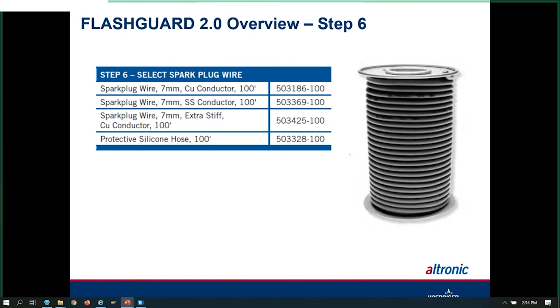But then the stainless steel second one down is the 503-369. We've had that for probably 15 years now, and we do sell quite a bit of it. But it's more used for the applications where you have a lot of H2S or a lot of corrosion. And that's basically a good choice, because the stainless holds up to the H2S, and it's not much tougher than the copper. That's more of a yellow metal that corrodes. So that one, the bright blue fluorescent jacket, kind of gives you an idea that is the stainless steel wire.